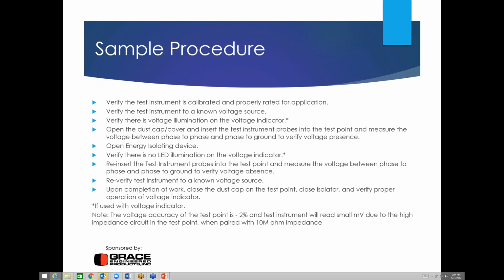That being said, we're going to continue to follow our facility lockout tagout procedures and do any other steps that are required. And then we're going to do our work, and when it comes time to bring that unit back online, we're going to basically reverse the process, bring the system back up, and verify that there is voltage on the voltage indicator. So that's a simple sample procedure.